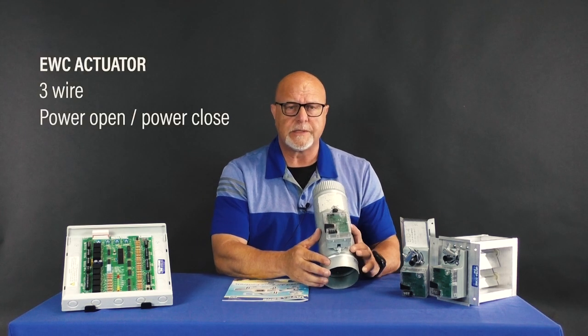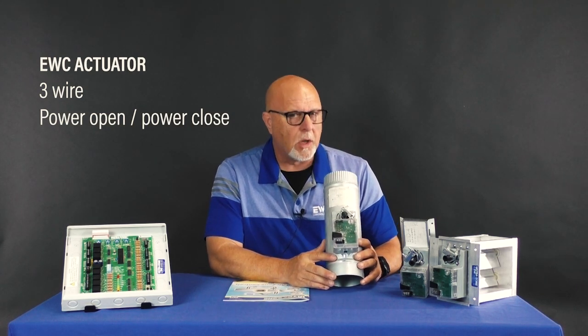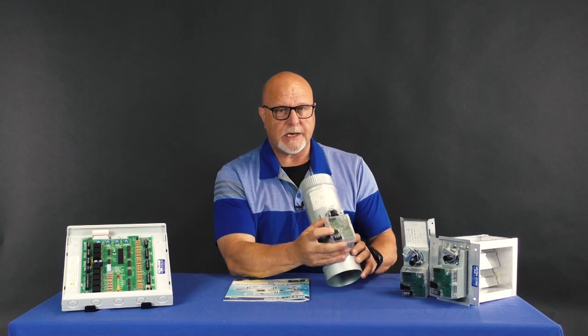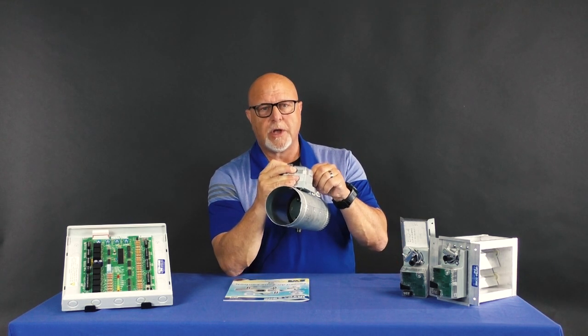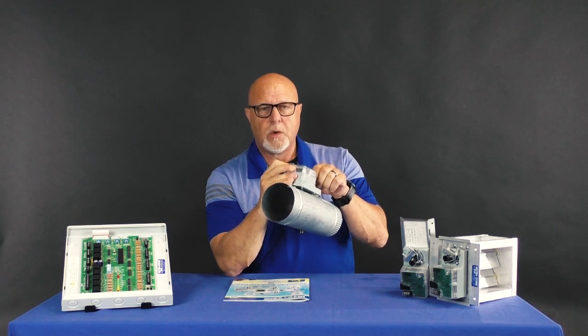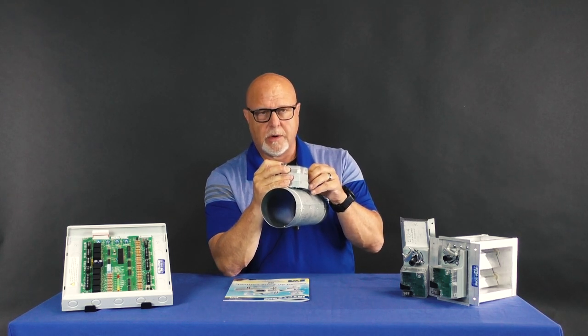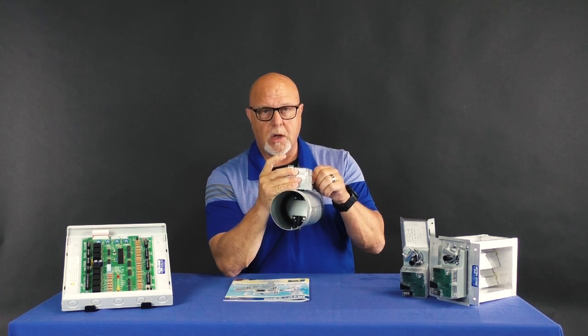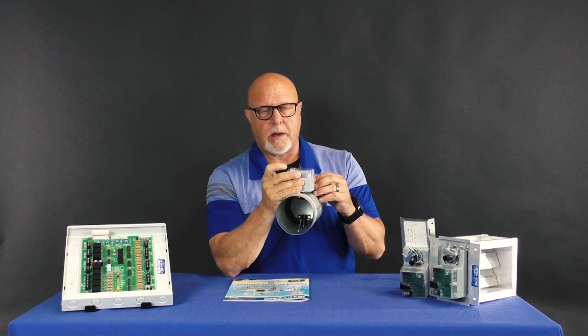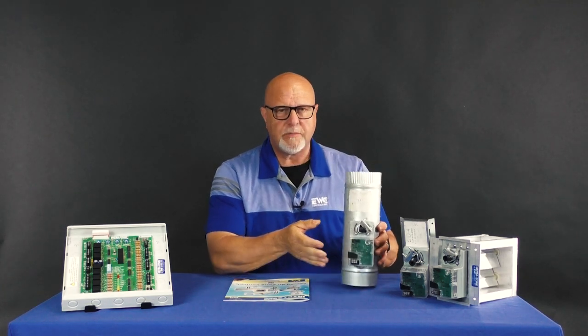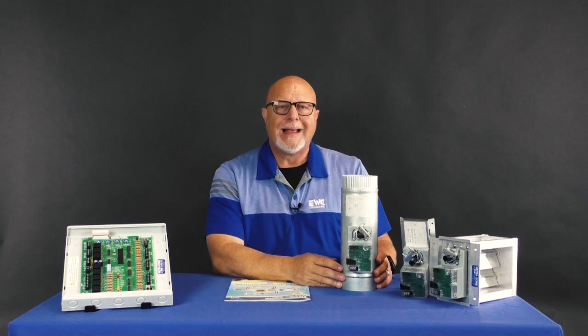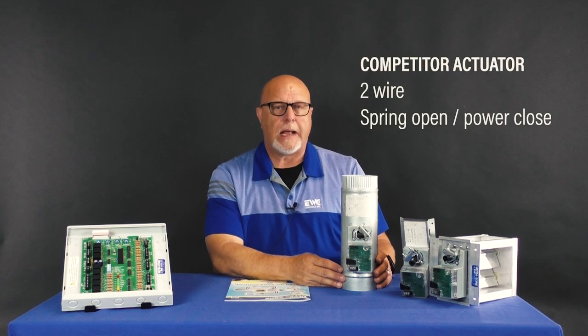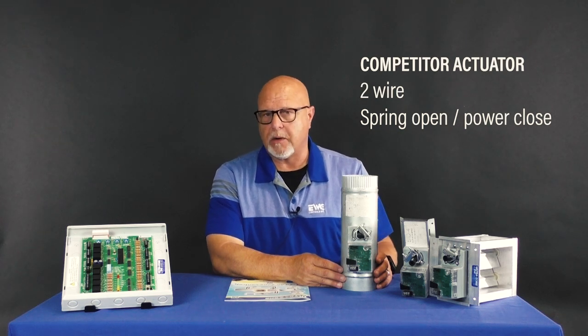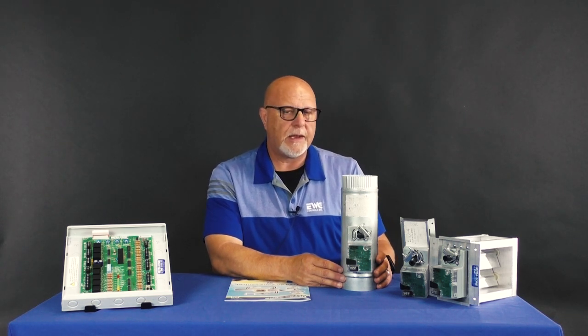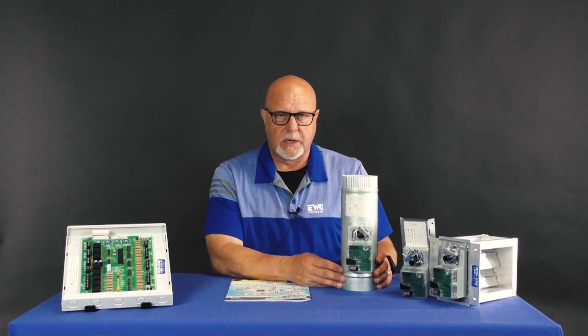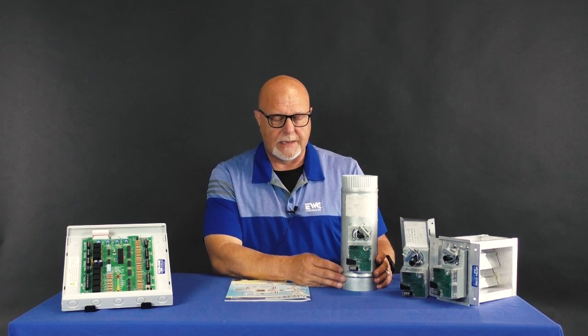First of all, I will point out that this is a 3-wire power open, power closed actuator. It is a 35-second travel time, meaning that it takes 35 seconds to go from fully closed to open. We will lock there and drop power to the motor. 35 seconds from fully open to closed, and we will lock there and drop power to the motor. Most of my competition out there in the zoning world has a 2-wire spring return actuator that springs open and powers closed. Constantly there is power on that damper that will, over time, reduce the lifespan of that motor because there is power on it all the time.